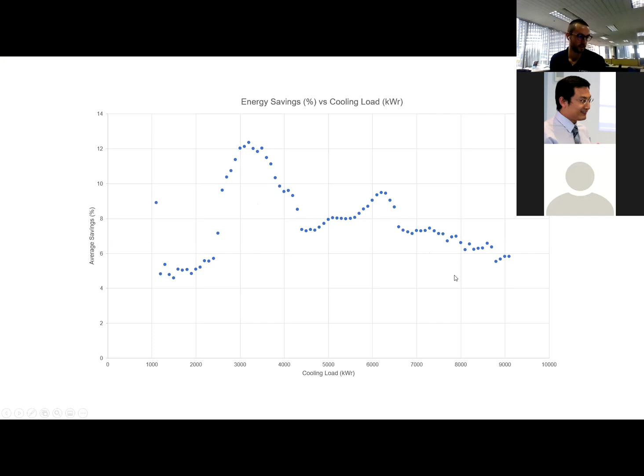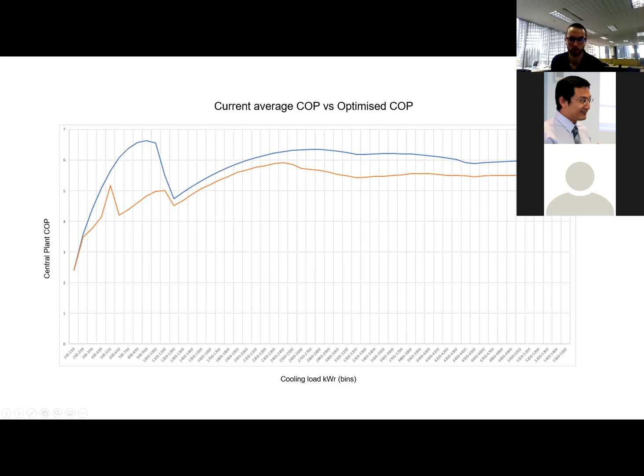And in terms of what that looks like, this is cooling load on the x-axis again, and we've got the central plant COPs. So we've compared here, sorry, these aren't labeled, what's the current average COP for each cooling load, which is this orange line here. And you can see the blue line is the optimized, or the model's idea of what the highest possible COP would be for those given cooling loads. And that difference shows up as the potential for improvement.